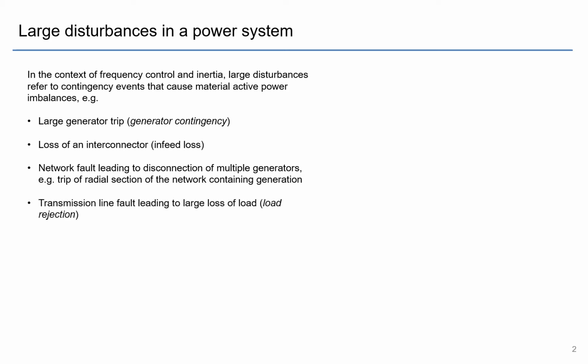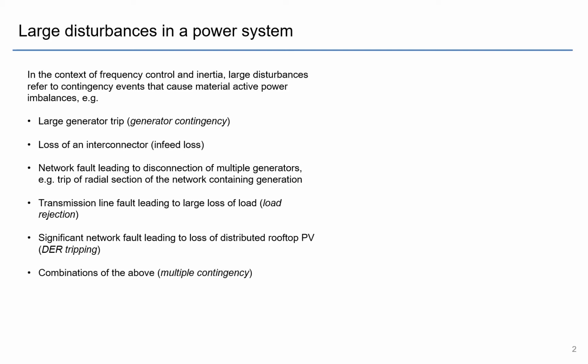A transmission line fault that leads to a large loss of load. So again, you might have a radial connection to a load and you have a fault on that line. Or alternatively, you might have a lot of lightning in the area that manages to trip a lot of load at once. And a significant network fault can lead to the loss of distributed rooftop PV, so DER tripping. This is an emerging risk that we'll talk about a bit later. Or combinations of the above, so multiple contingencies.